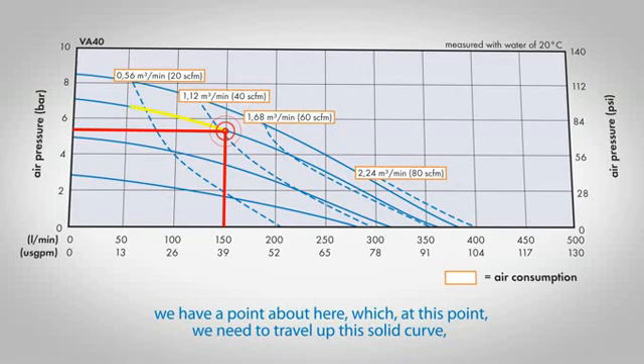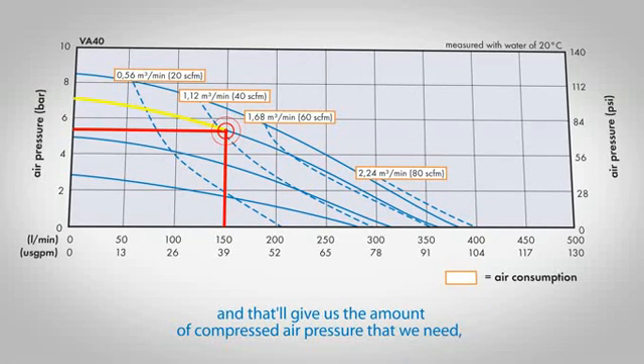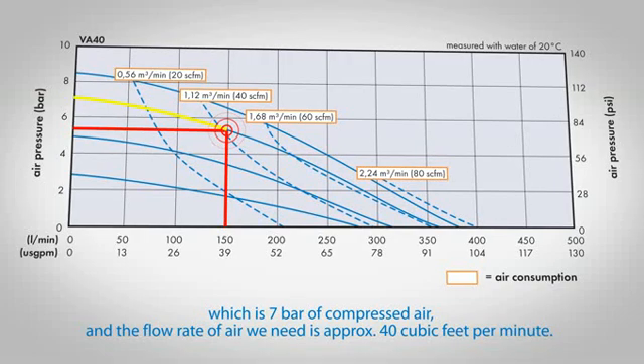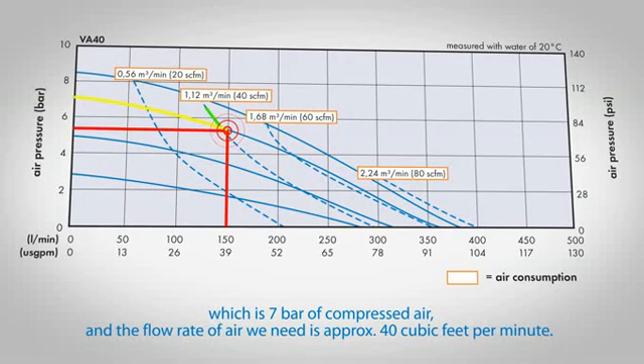Which at this point we need to travel up this solid curve, and that'll give us the amount of compressed air pressure that we need, which is 7 bar of compressed air, and the flow rate of air we need is approximately 40 cubic feet per minute.